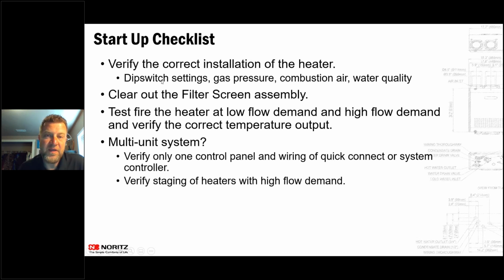Every manufacturer has different settings that you have to set within the unit to make sure that the unit is set for the install that you're in. With our units, we have dip switches. You would set a dip switch for the elevation and a dip switch for your vent run. And if you're pulling combustion air from inside the house, you'd flip a dip switch. We have a really easy app that you can put that into and it tells you exactly what dip switches you need to press, so you don't have to go through the manual. But if you don't have those dip switches set correctly, a lot of times it'll actually run for quite a while before it'll start throwing error codes, but it will start throwing error codes. So the dip switch settings need to be set correctly.